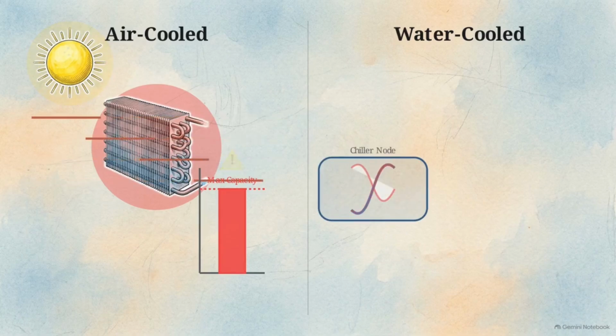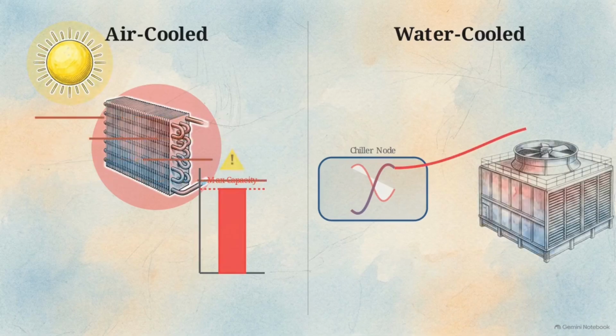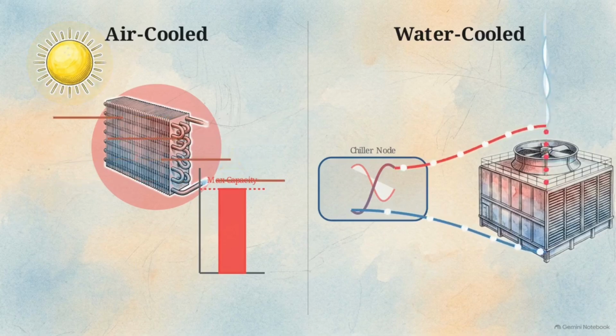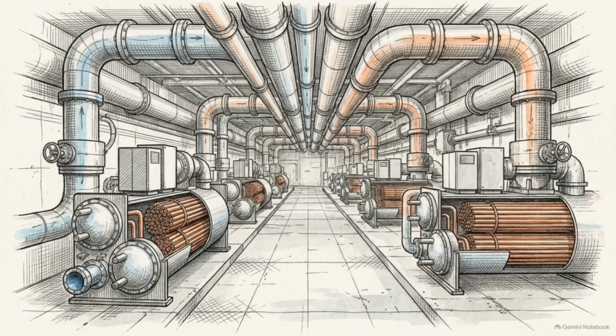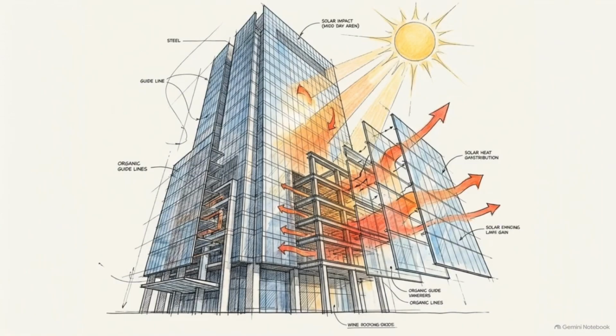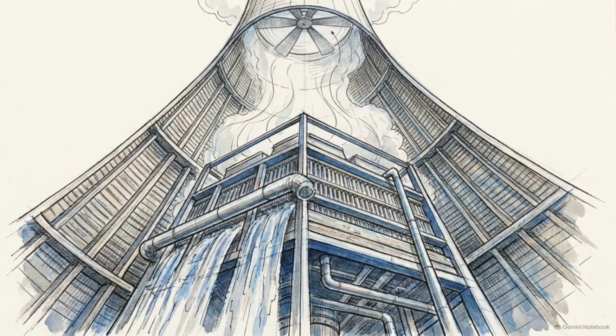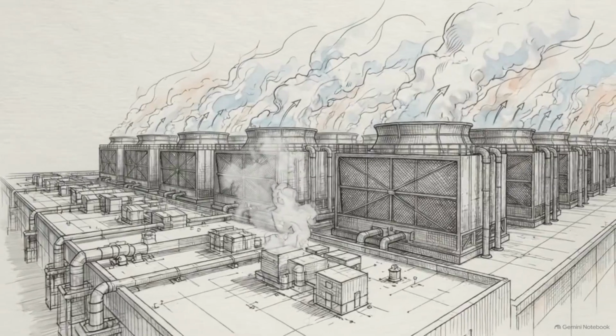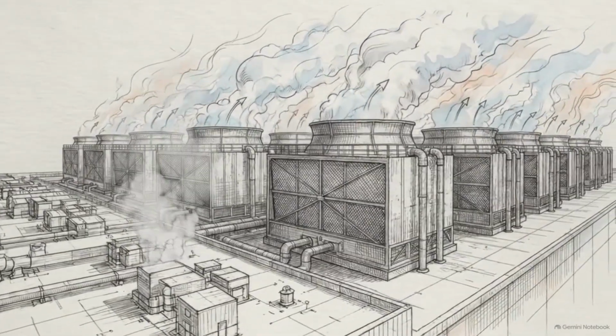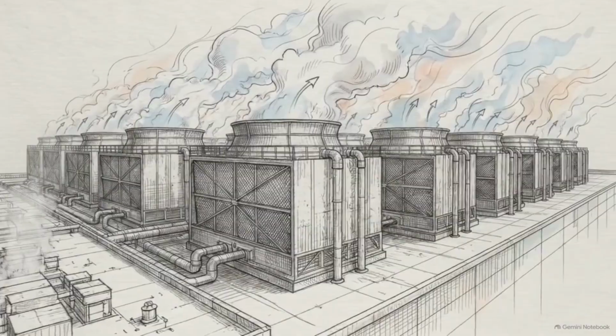On the right side, we see the water-cooled architecture required for megawatt-scale industrial loads. Here, the condenser interfaces with a secondary external water loop. Water is far denser than air and absorbs heat much more effectively. This condenser water absorbs the heat and physically transports it away from the main chiller unit to a separate external structure, the cooling tower. Inside the cooling tower, the system leverages the latent heat of water evaporation. A small portion of the water is allowed to evaporate, absorbing massive amounts of heat and finally rejecting that thermal energy into the atmosphere. The entire water-cooled process follows a strict chain. Heat moves from the building into the chiller, transfers to the condenser water, travels to the cooling tower, and disperses into the atmosphere. Engineers select this complex, water-reliant architecture over simpler air cooling when the sheer volume of heat demands a more efficient thermodynamic sink.